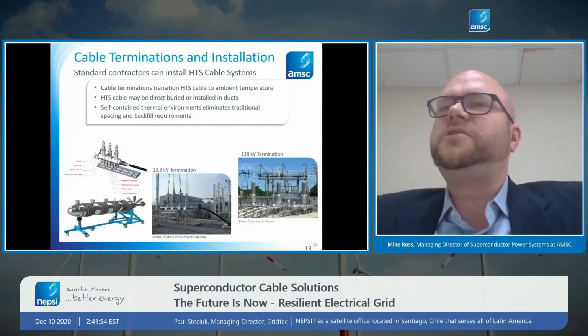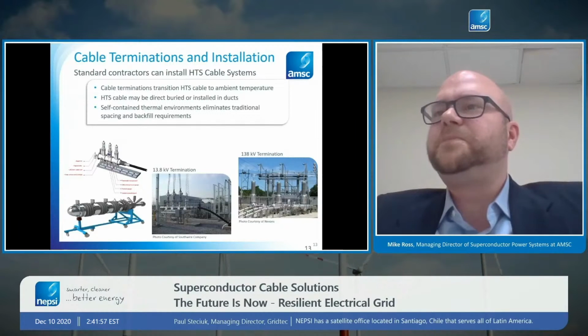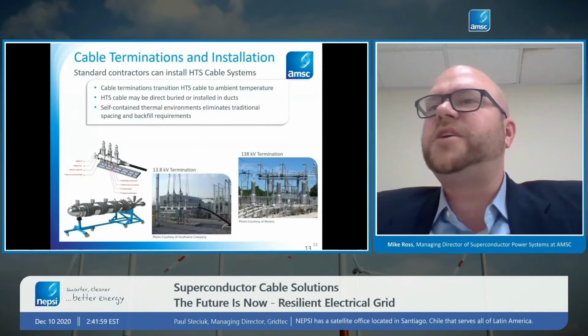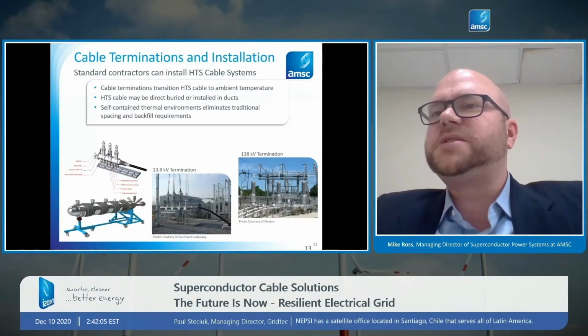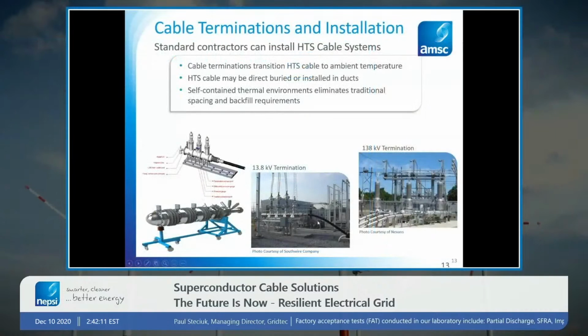The final major component of the systems is the terminations. So the terminations is where you transition from the conventional grid into the superconductor cable. In the middle here, and I've got a better slide of this coming up, is the original termination. This was installed in 2006 at AEP, a utility in Ohio, as a demonstration project. And so what you can see is that there are 3 phases coming in. So phase A, phase B, and phase C are dropping down into the termination in our single superconductor cable. This is 13.8 kV, comes out the end.